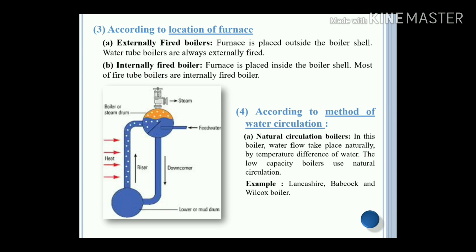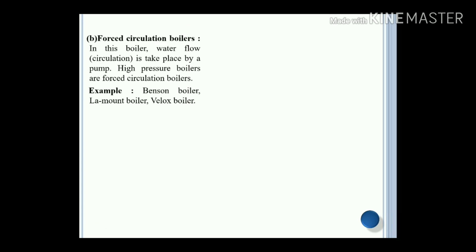Fourth, according to the method of water circulation. Natural circulation boiler: water flow takes place naturally due to the temperature difference of the water. Low capacity boilers usually use natural circulation. Examples: Lancashire boiler, Babcock and Wilcox boiler. Forced circulation boiler: water flow takes place by a pump. High pressure boilers are always forced circulation boilers. Examples: Benson boiler, Velox boiler, LaMont boiler.